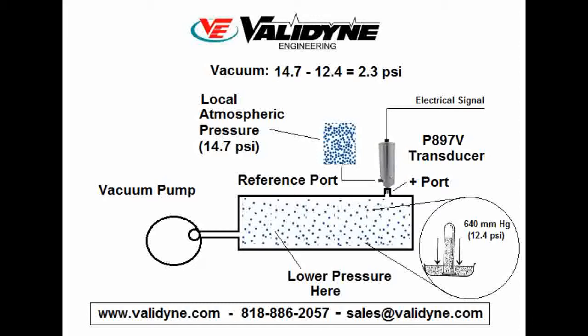In this example, measuring the absolute pressure inside the tank and controlling the pump on this signal would cause problems, because the actual value of the atmosphere would not be taken into the measurement. Pumping down to 12.4 PSIA each day, when the atmosphere was as high as 15.2, would cause a much greater vacuum.